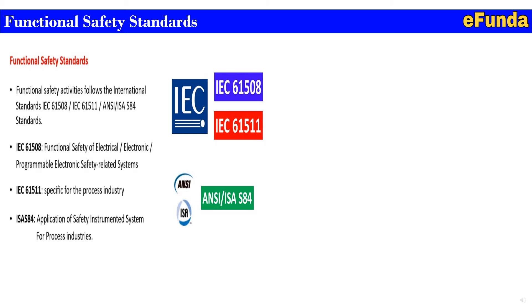Primarily, functional safety activities follow international standards: IEC 61508, IEC 61511, and ISA S84. Mainly, IEC 61508 covers functional safety of electrical, electronic, and programmable electronic safety-related systems. IEC 61511 is specific to the process industry, and ISA S84 is also applicable for the process industry.